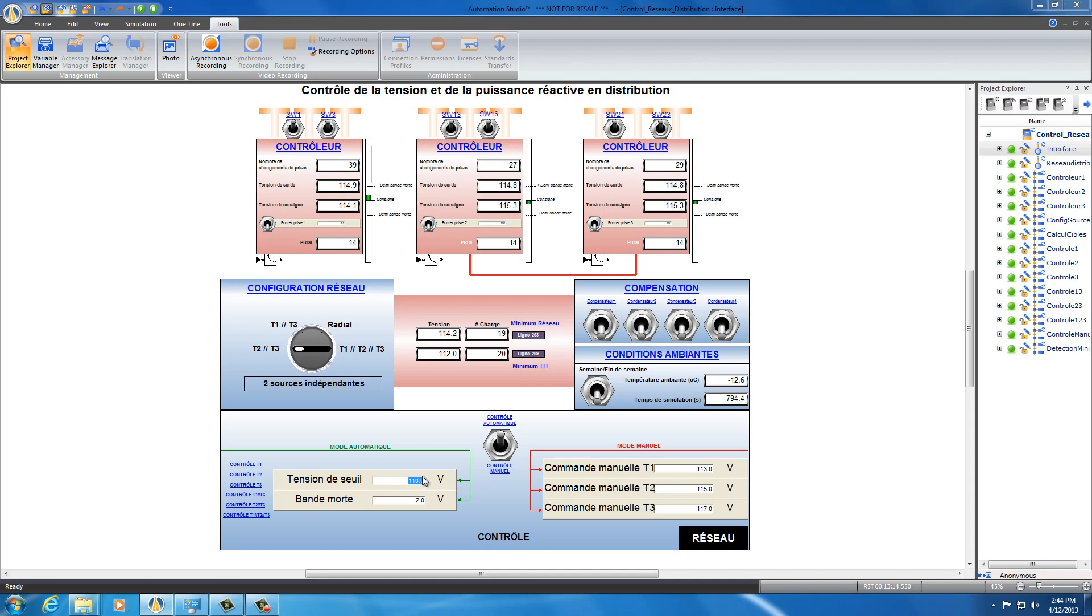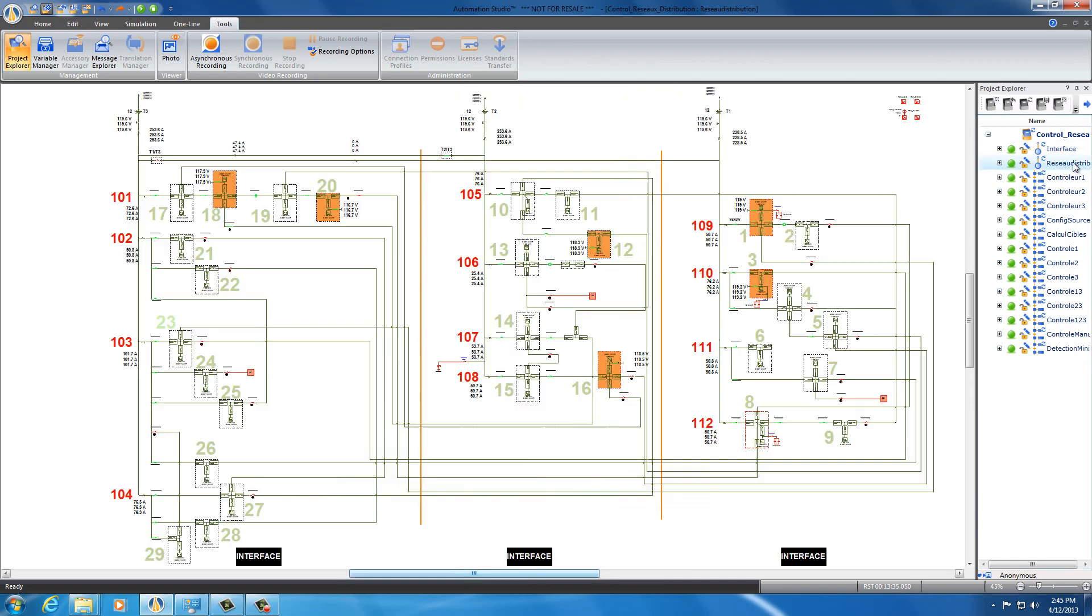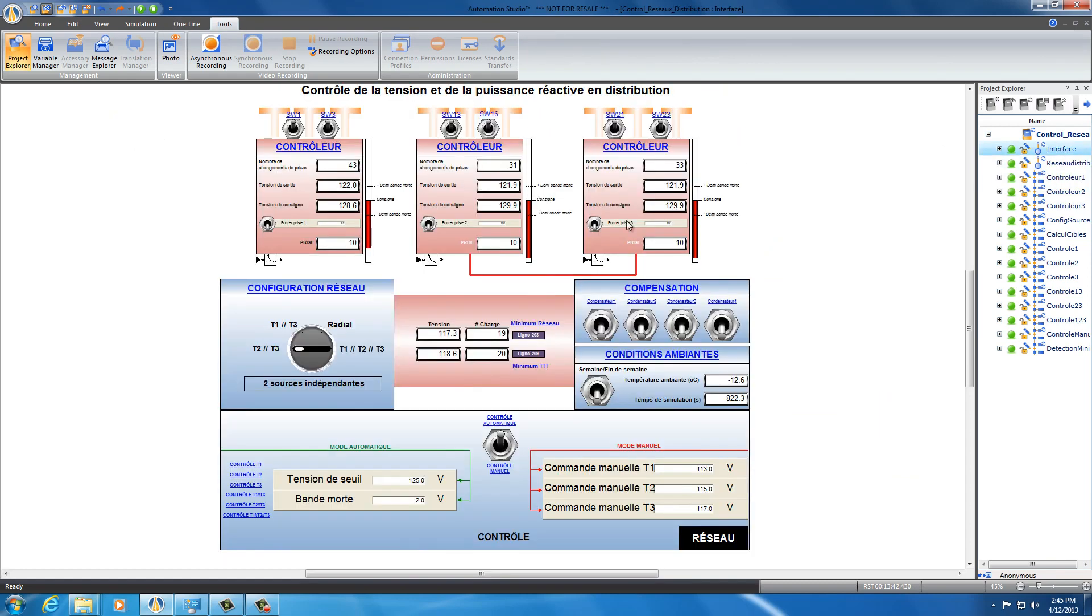Let's put, for example, 125 volts as a minimum voltage. So now to get 125 as the minimum voltage, we need an output voltage of 129.9 at transformer T2 and T3. So here for T2 and T3, we need a 129 output voltage in order to get 125 as a threshold minimum voltage.